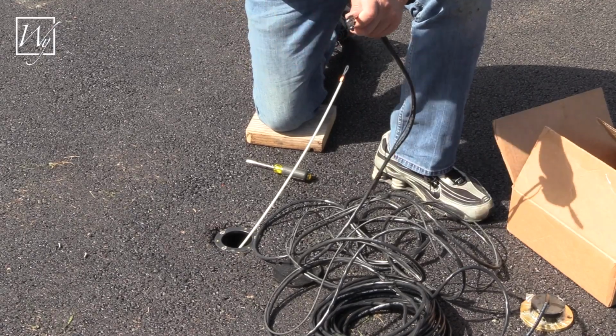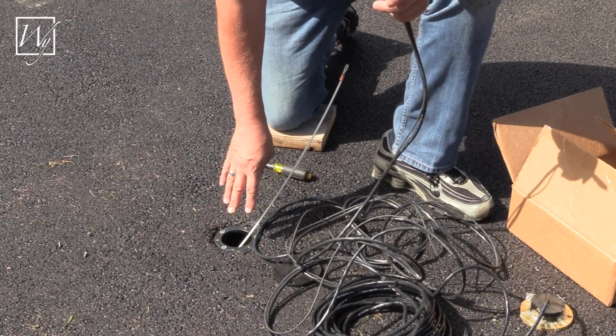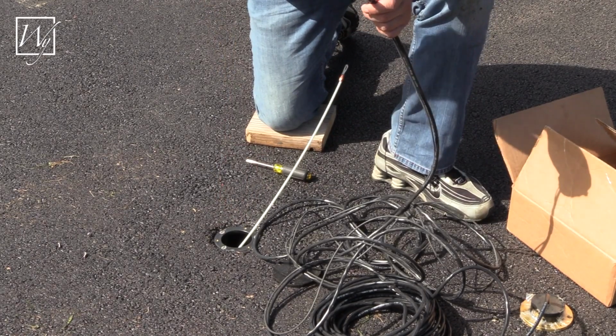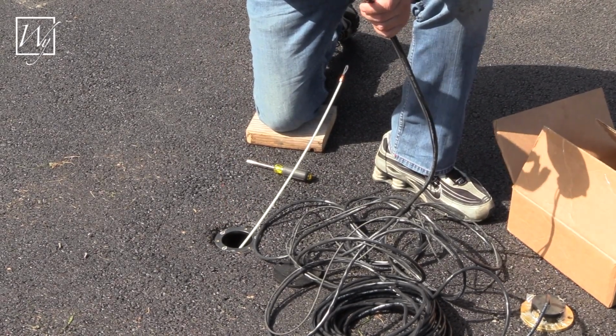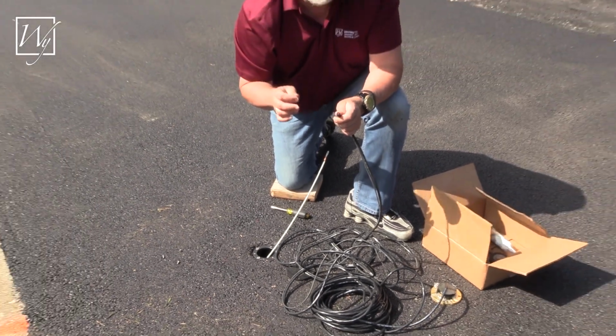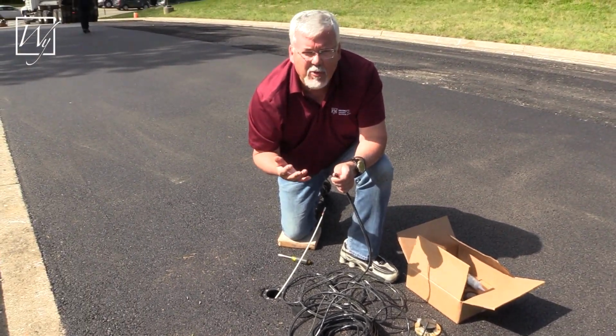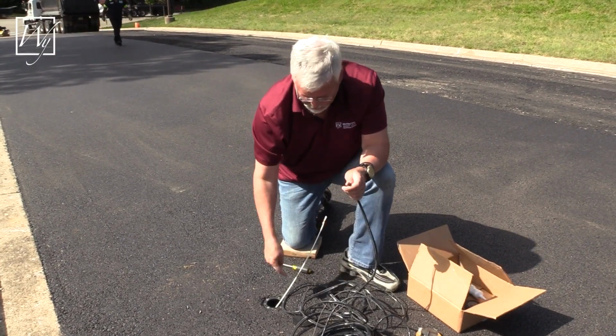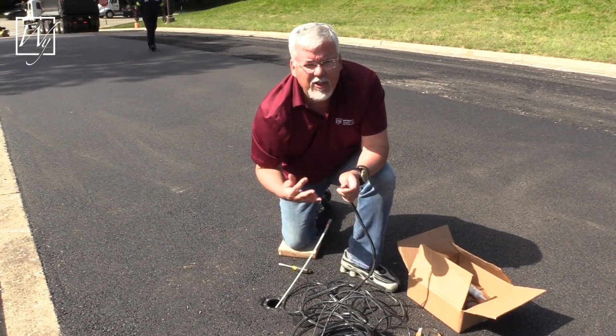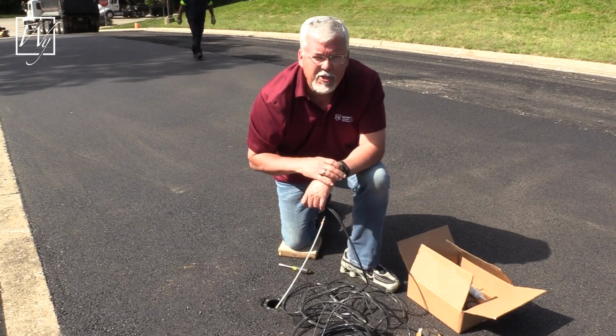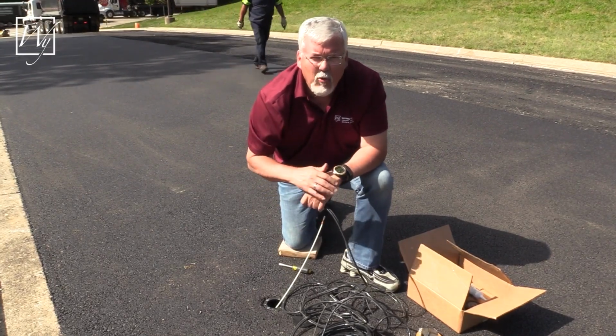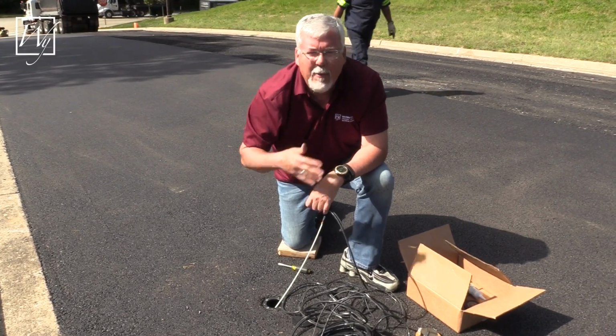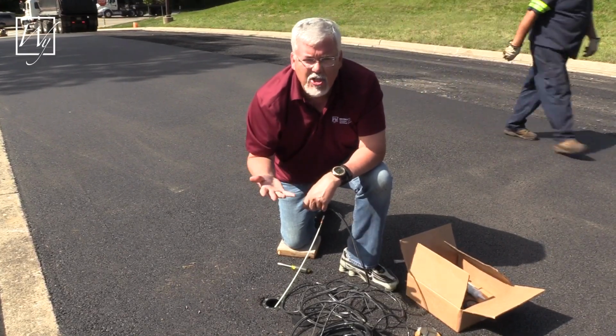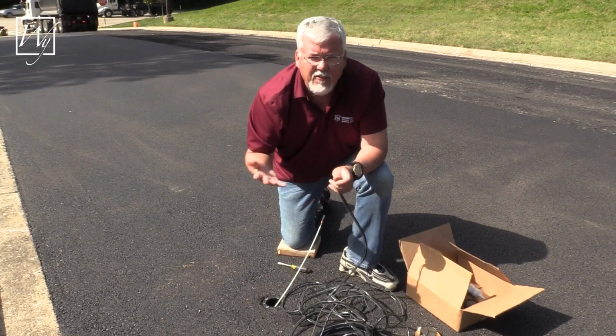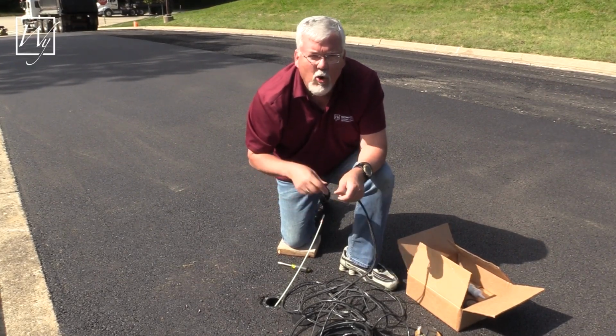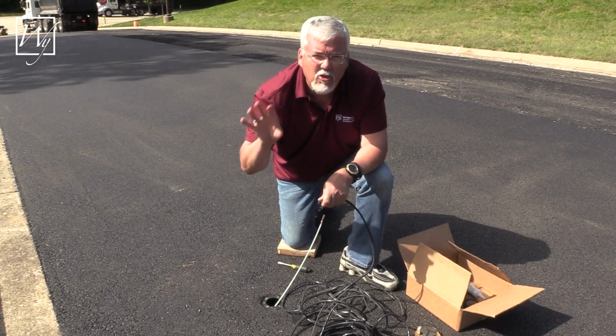We actually have two sensors in here. One is the asphalt sensor, which tells the controller when the temperature gets below 38 degrees, or whatever the set point is, and whether there's precipitation present. There's also a sensor placed a bit further along, as we've already seen in the video — the over temperature sensor. It tells the controller when the slab reaches a certain temperature, and if we want it to shut off at, say, 60 or 50 or 70 degrees, that over temperature sensor is always talking to the controller.